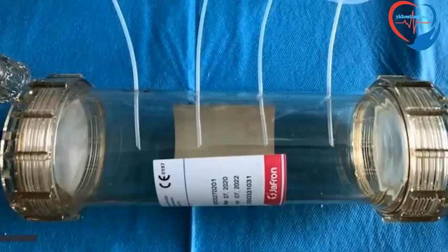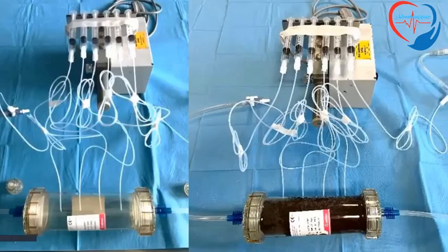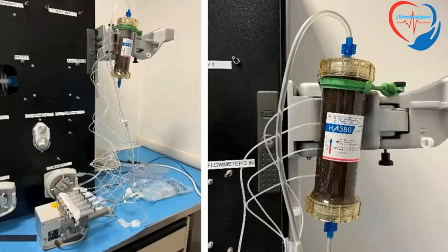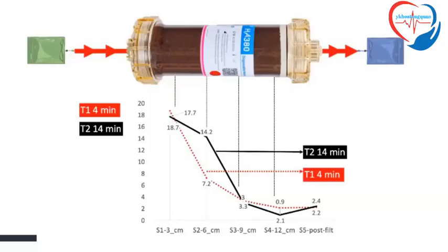We specifically utilized the experimental setup in our institution with the system to provide simultaneous withdrawing of blood components from the circulation. And you see, thanks to this machine that we have developed in our institute called Galileo, we have tested the mass transfer zone. And it is interesting to see that practically the mass transfer zone is shorter than 1/3 of the length of the cartridge, showing a very good design of the cartridge.